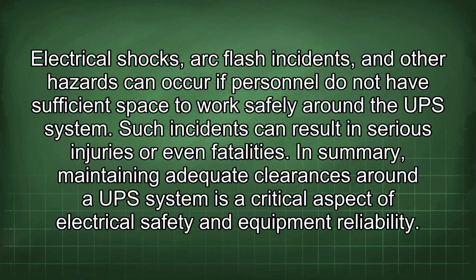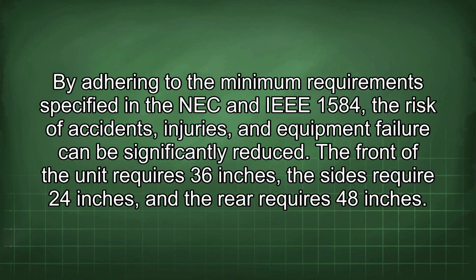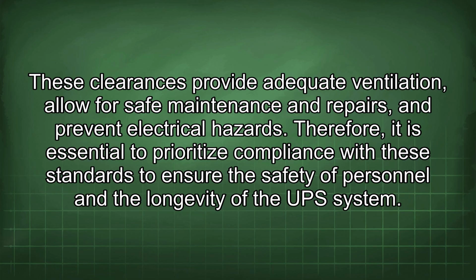In summary, maintaining adequate clearances around a UPS system is a critical aspect of electrical safety and equipment reliability. By adhering to the minimum requirements specified in the NEC and IEEE 1584, the risk of accidents, injuries, and equipment failure can be significantly reduced. The front of the unit requires 36 inches, the sides require 24 inches, and the rear requires 48 inches. These clearances provide adequate ventilation, allow for safe maintenance and repairs, and prevent electrical hazards. Therefore, it is essential to prioritize compliance with these standards to ensure the safety of personnel and the longevity of the UPS system.